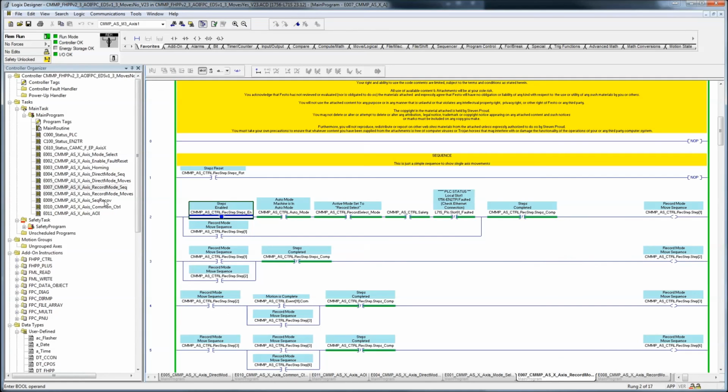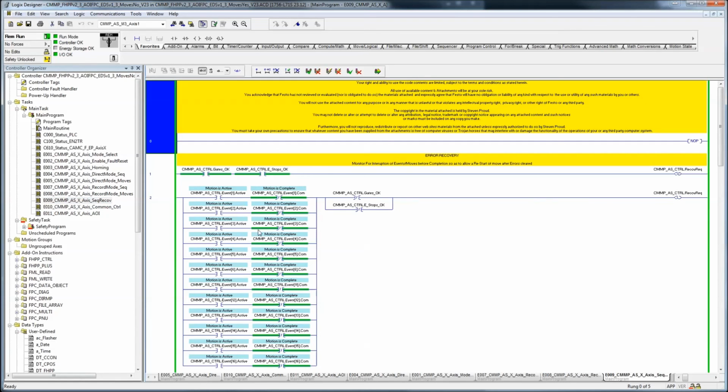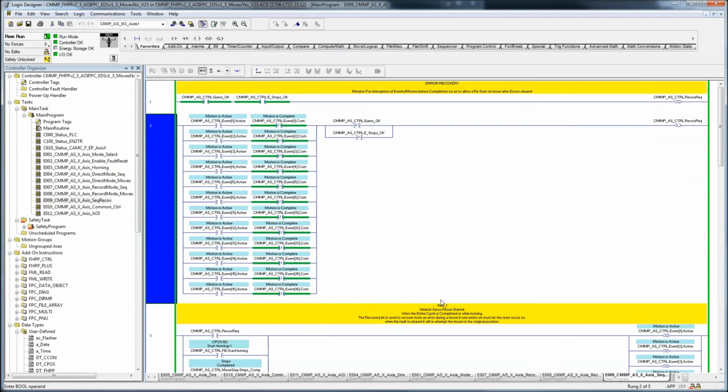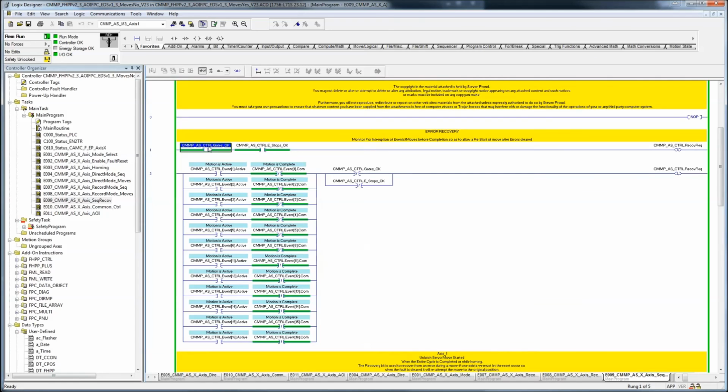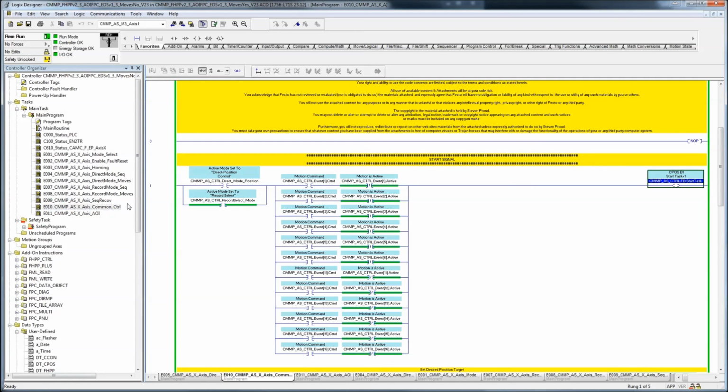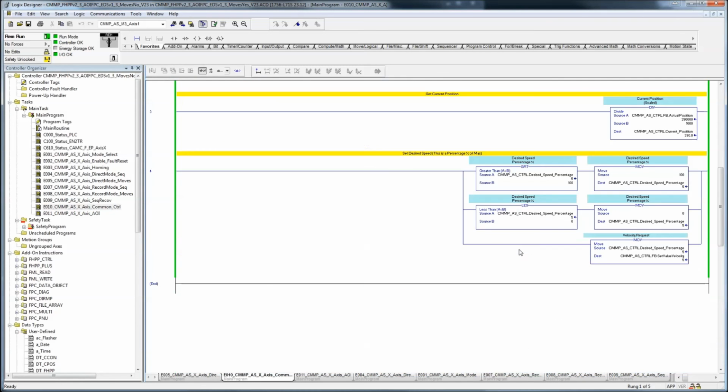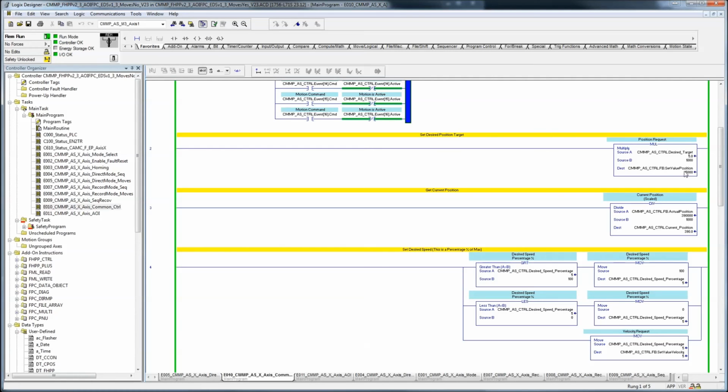And there's the sequence recovery bit, whether you care to understand how it works or not. Basically, if at any point you drop the gates or e-stop, the code is designed such that when you reset the gates or e-stops, and both are okay, then it'll pick up the last movement it was in the middle of and continue on its way, off and running. Okay, so that's the simplicity of it all.